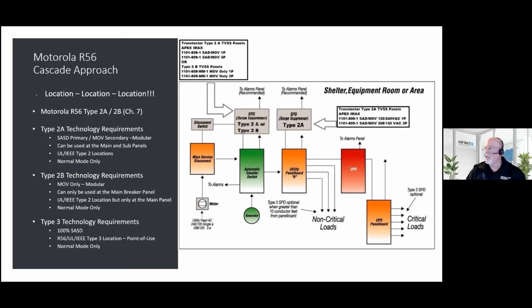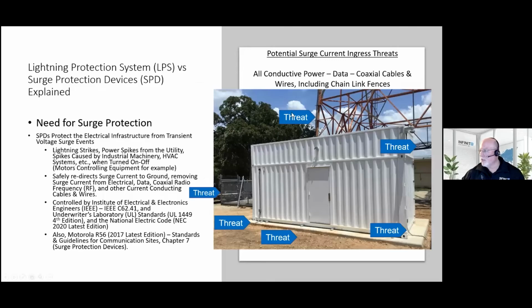So if you use a cascading plan like this, with a surge arrestor at strategic panels, then you're dividing and conquering that surge current, but more critically, the critical gear will be properly protected. All of these little arrows show you different sources of where surge currents can be induced and brought in. And in this scenario, the chain link fence needs to be grounded. The metal building needs to be grounded. Any cables coming in, every single thing that conducts, if you don't put a protector on it, that's the back door for the surge current. And now you're replacing gear.